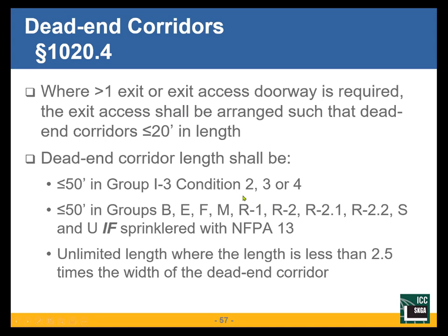Even though it may be a hotel, apartment building, assisted living space, I have to use NFPA 13, even though 13R may be appropriate. I don't get the credit for the 13R system with regard to this.